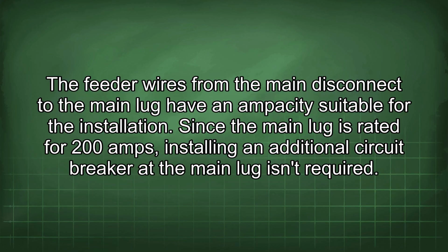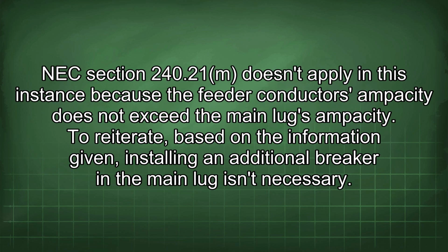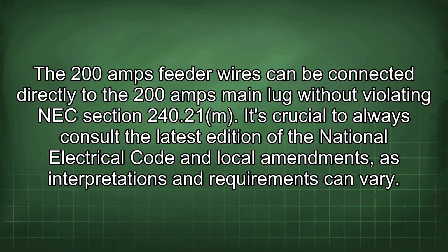Since the main lug is rated for 200 amps, installing an additional circuit breaker at the main lug isn't required. NEC Section 240.21 doesn't apply in this instance because the feeder conductor's ampacity does not exceed the main lug's ampacity. To reiterate, based on the information given, installing an additional breaker in the main lug isn't necessary. The 200 amps feeder wires can be connected directly to the 200 amps main lug without violating NEC Section 240.21.